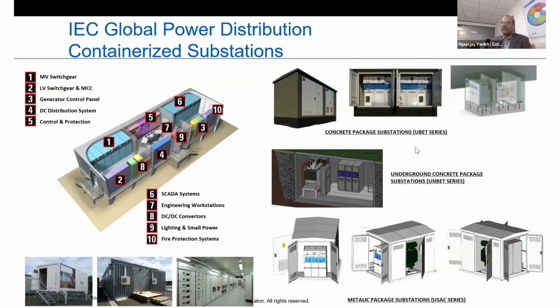Eaton partnered with BESCOM for a pilot installation where, right under the footpath on the streets, the substation was created using the solid insulated switchgear I mentioned, because in an underground substation, if there's a gas leakage, it may not be evacuated easily. This system eliminates the need for dirty pole-mounted structures, transformers, or cabinets sitting on the streets. It all goes completely underground, and Eaton will be happy to partner with utilities to expand this concept.